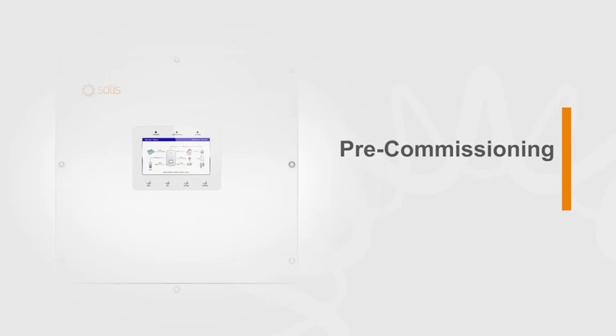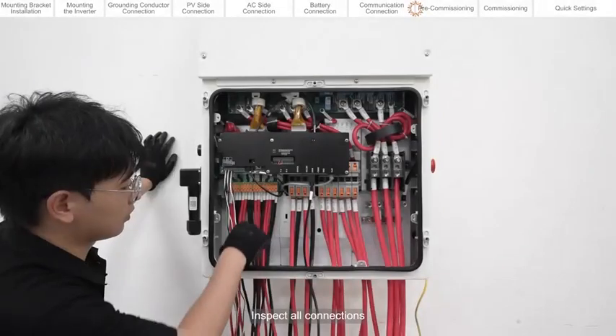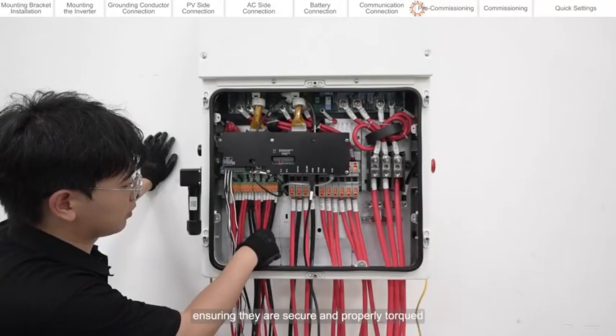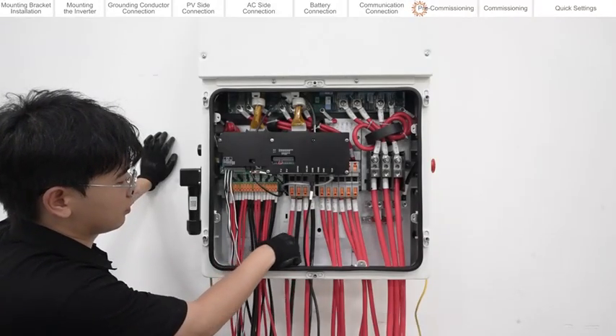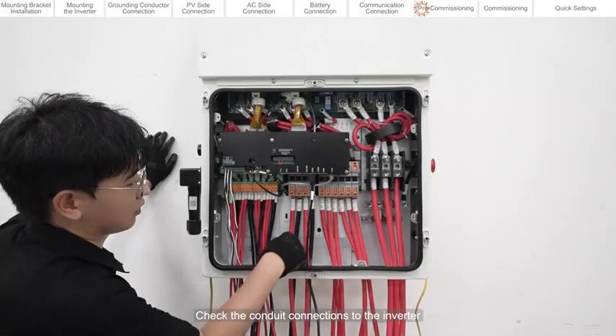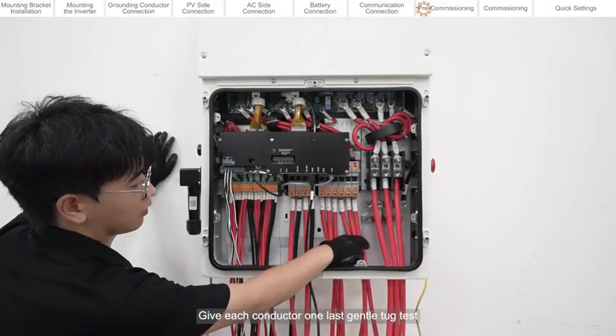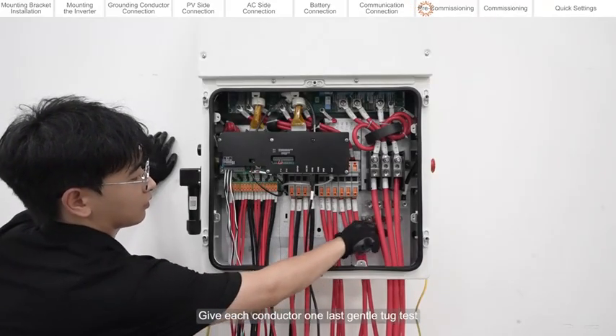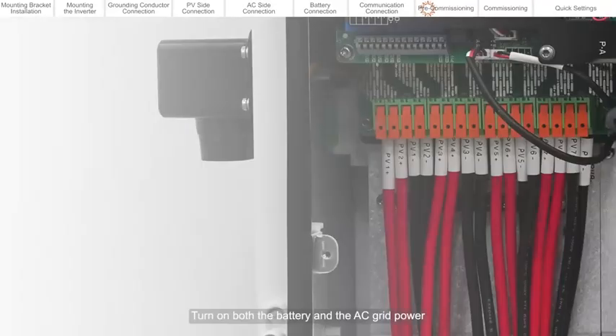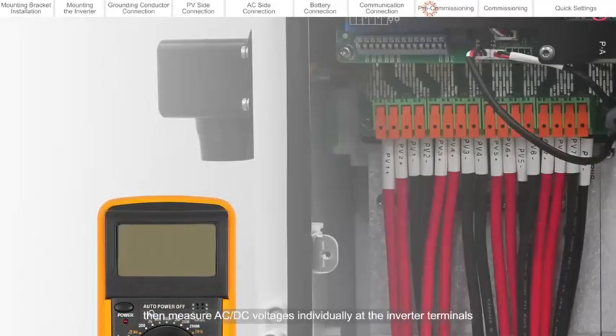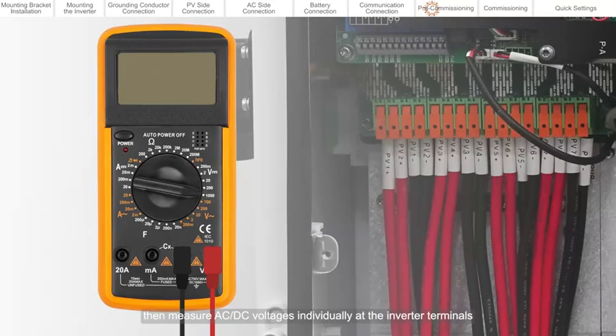Pre-commissioning. Inspect all connections, ensuring they are secure and properly torqued. Check the conduit connections to the inverter. Give each conductor one last gentle tug test. Turn on both the battery and the AC grid power, then measure AC and DC voltages individually at the inverter terminals.